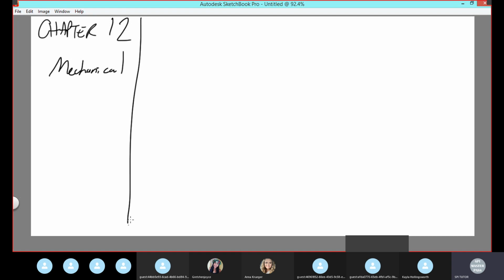Okay, the mechanical transducer, we don't use it. It's a single crystal transducer. It has one crystal. We're too ballers for that. We want hundreds of crystals. Okay, so this is a single crystal transducer. It is completely mechanical. So there is nothing electric about it. It gets focused mechanically, and it is steered mechanically.